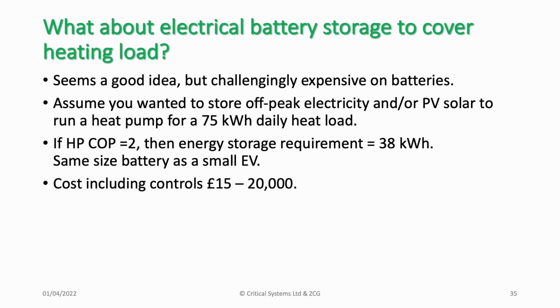Seems a good idea, but actually if you look at the numbers, it would probably be challengingly expensive on batteries. If you assumed you wanted to store off-peak electricity and/or photovoltaic solar energy to run a heat pump for a 75 kilowatt hour daily load, then you would need an energy storage requirement of 38 to 40 kilowatt hours. This is the same size battery as a small electric vehicle, and the cost of a battery installation like this could be 15 to 20,000.